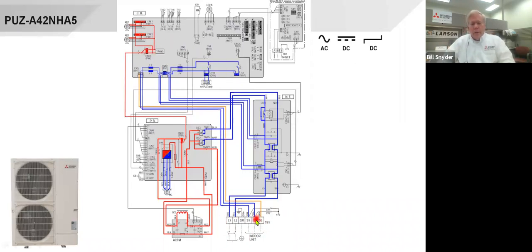But the odd thing here is we're using S2 for power, and we're also using it as a common signal for the S3, which is a DC pulsing signal. So you can't mix these up. S1 on the outdoor unit has to go to S1 on the indoor unit, and S2 to S2 and S3 to S3. You can't mix them up. It's not like L1 and L2, where you can mix them up and it doesn't make any difference. On this, it does make a difference. So just be careful with that.